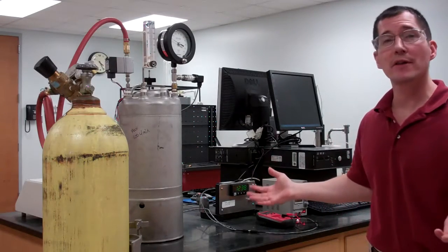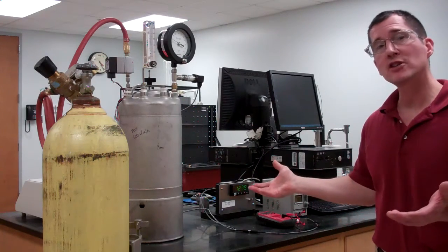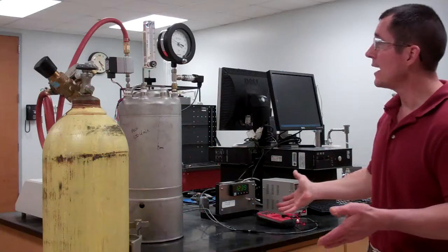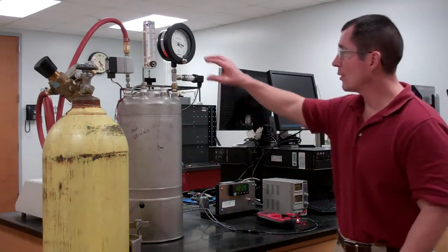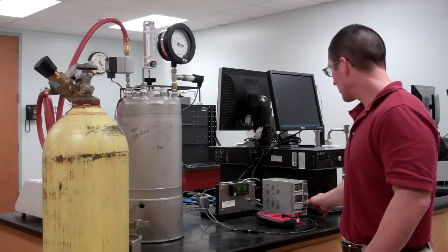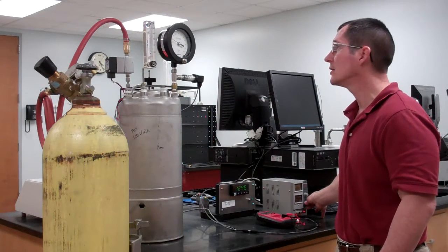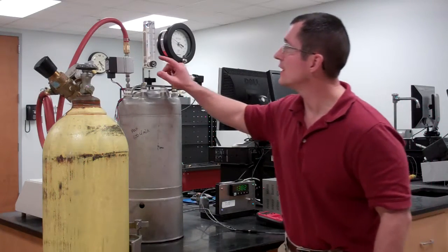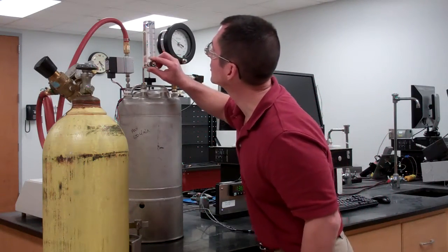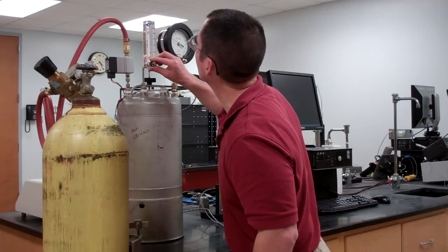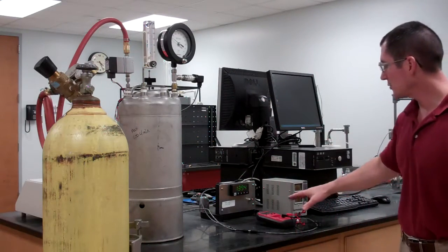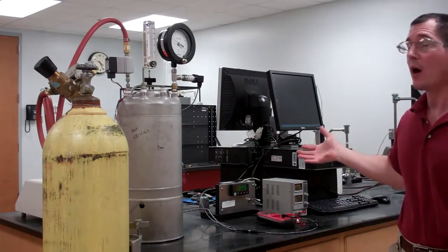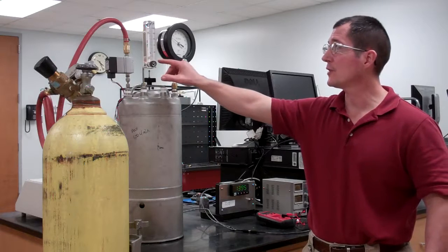Well, that's going to be part of the control problem. What is our range of control on this particular apparatus? With, say, the flow rate coming out at 20 liters per minute, and we want to get the pressure back at 15, we're going to have to increase the signal to the final control element. Now, of course, as we did that, the flow rate may increase a little bit, so we may have to dial it down just a little bit to get back at 20. But you can see the difference in signal that you have to apply to the final control element, the difference in power, when you actually have some flow going out.